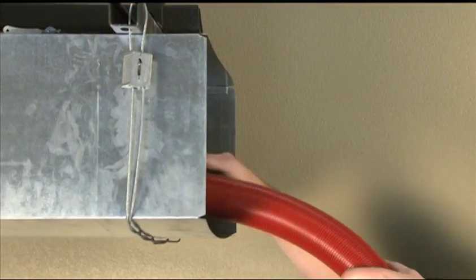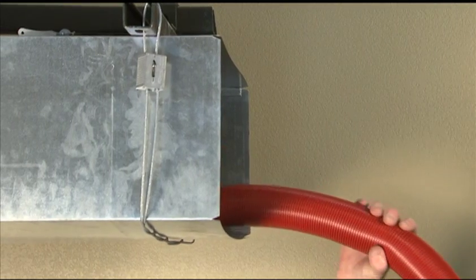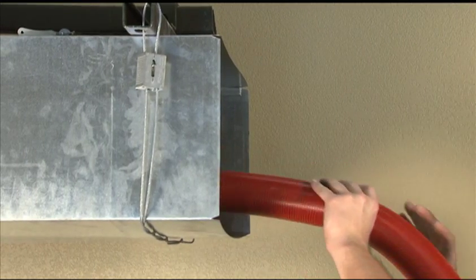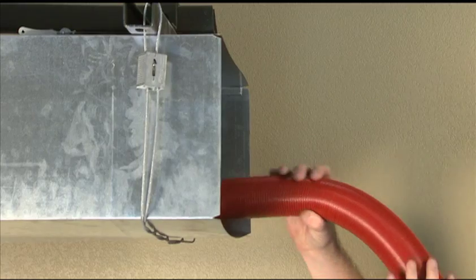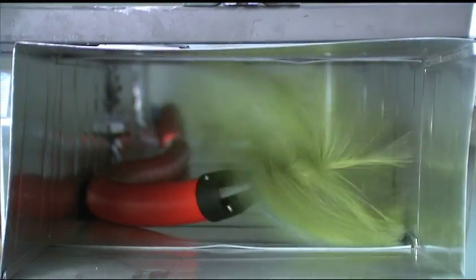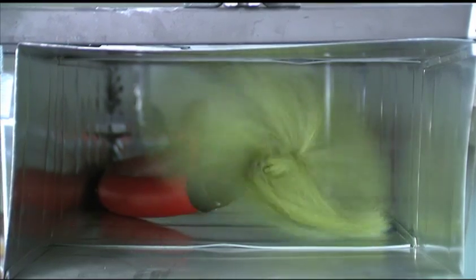The first method to use, and the one that takes care of 99% of it, is to simply push the hose in about 6 to 12 inches and give it a quick firm pull backwards, and that allows the brush to center in the air duct and come backwards over whatever is obstructing it. The next thing is, you can twist the hose clockwise or counterclockwise. Basically twist the hose, and that allows the hose to act like a corkscrew, and any obstruction, it will actually walk over. The other option you have is to change brush direction via the brush control.